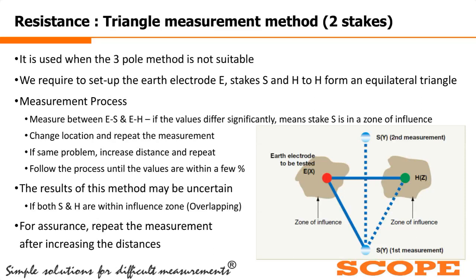So by meeting these conditions, we will measure these two earth resistance values, and if the two earth resistance values between ES and EH differ from each other by a very high margin, then we have to change the position of S from the first position, and again we have to repeat the measurement. If the same problem remains, then again increase the distance and again repeat. So manual intervention is required in this type of two-stake method. This method has very good accuracy, but as it is a trial and error method, it is not that much used in practical scenarios.